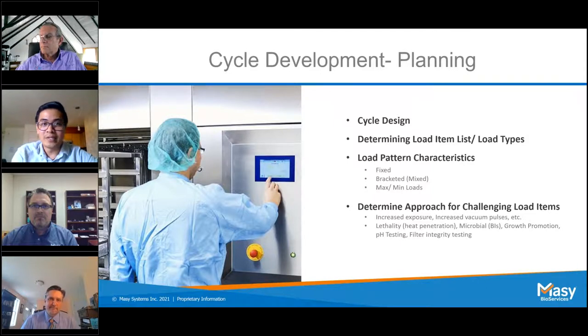So after going through your load pattern characteristics and deciding what pattern is required for your process, we move into this next phase of the cycle development phase, which is planning the approach for challenging the load items. Typically in this stage, the empty chamber mapping that we will later execute provides us with a lot of information as to how we will challenge the load items, as this is where we will find out where our cold spot is in the autoclave, which we discussed a lot earlier. This helps later in the execution stage as it will tell the executors where to place our hardest to heat item.